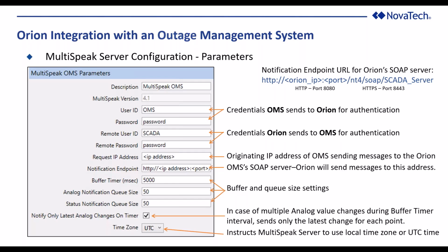Finally, the buffer and queue size are typically best left alone unless you have a reason for changing them. Lastly, there's the option that says notify only latest analog changes. Based on the settings on this screen, the buffer timer is set to 5,000 milliseconds, or 5 seconds—it will check and send analog changes every 5 seconds. If a specific analog point has multiple changes during that time period, checking this box will send only the latest change for that point, instead of sending a whole bundle of changes that occurred over that period.